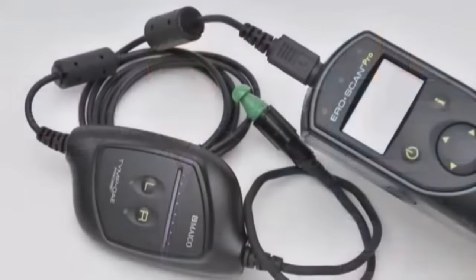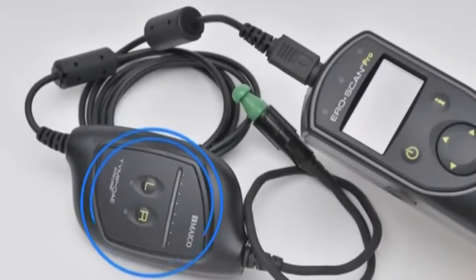Once you have the proper probe tip inserted into the patient's ear canal, you can use the up-down arrows on the navigator to choose the desired protocol from those available in the main menu. Selecting either the right or left ear with the navigator starts the testing process. For ease of use, the instrument always defaults to the last test protocol used. Remember, the tympanometry protocols will only appear in the main menu when the TYMP OAE probe is attached and recognized by the Ero Scan Pro. For detailed information on the protocols available in your unit, please refer to your operating manual.